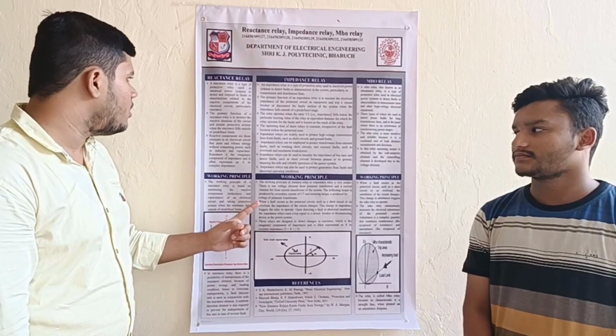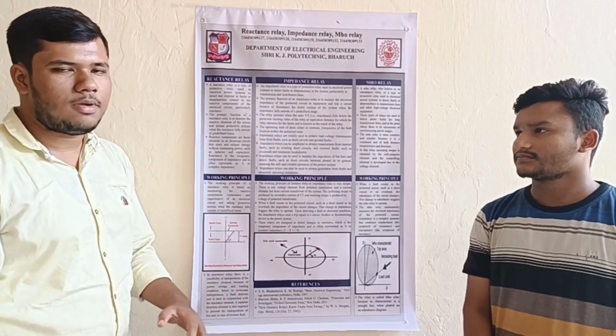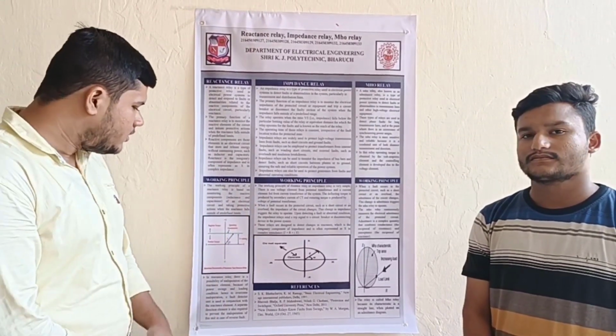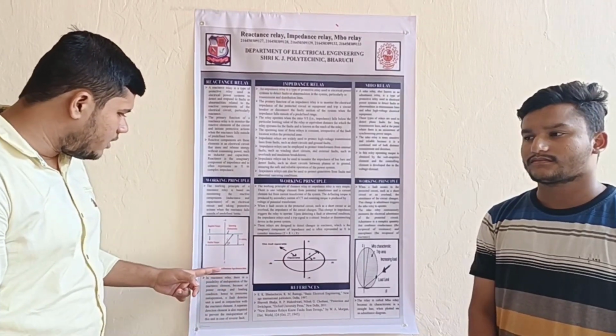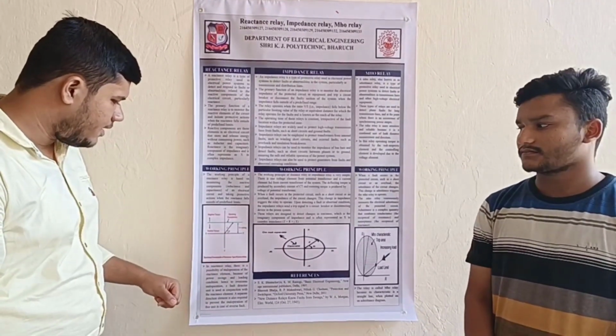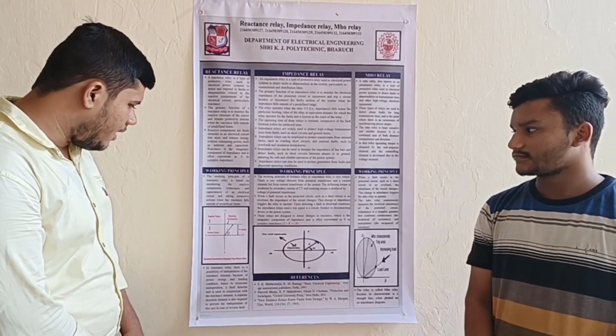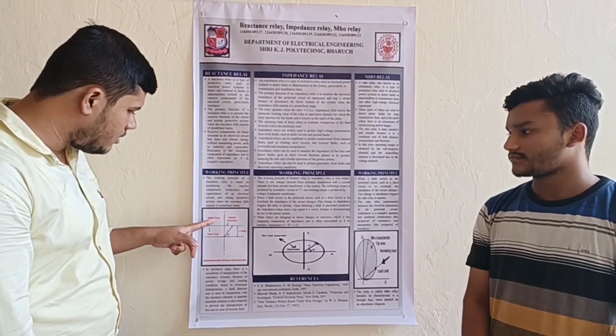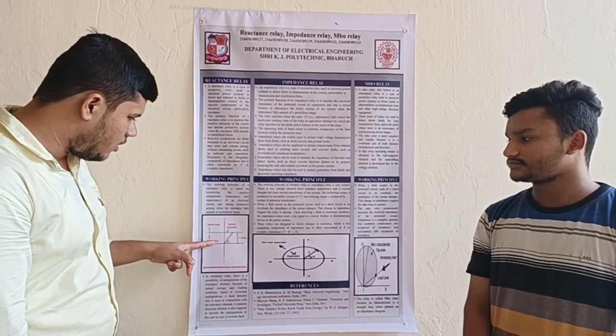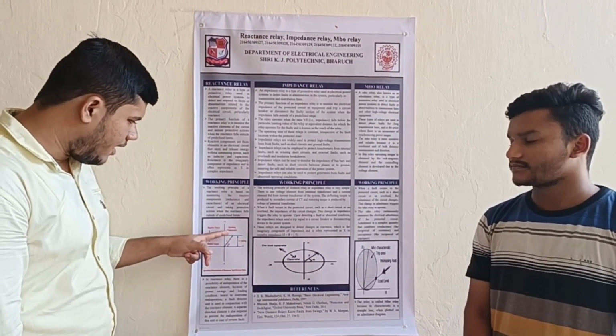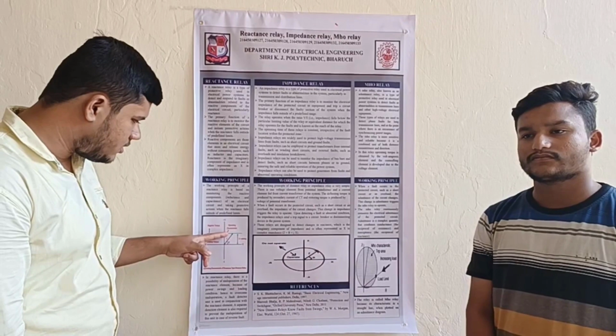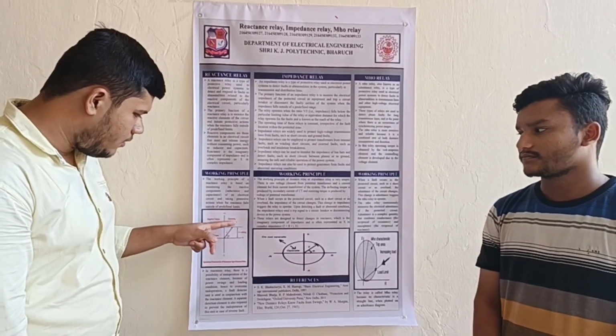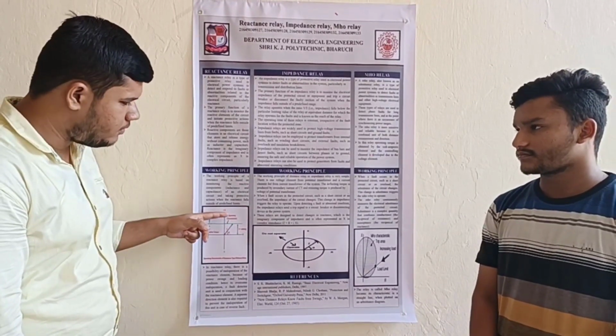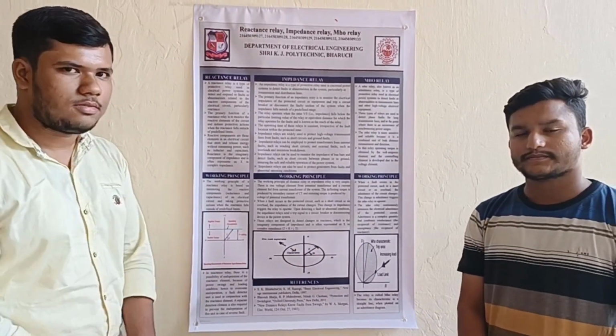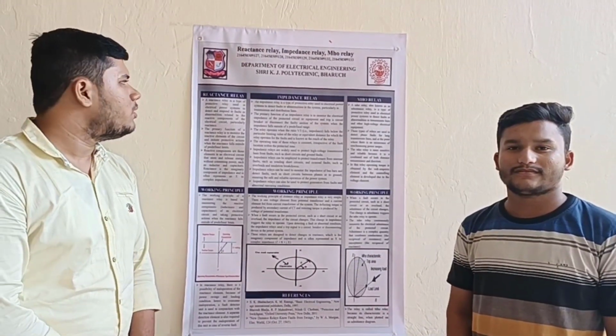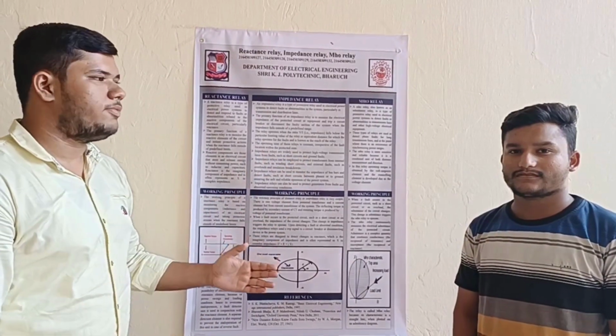Now, the working principle of reactance relay. The working principle of reactance relay is very simple. As you see in this figure, here is the operating characteristic of reactance relay. In this operating characteristic, here is the negative torque, and here is the positive torque. This figure is fully based on the operating characteristics. Now the impedance relay is explained by my friend Pratham Gandhi.